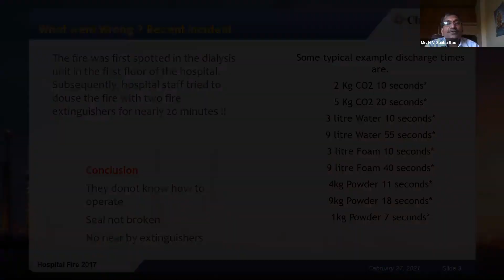From accidents we've had the chance to investigate and the data we've collected, the first fundamental thing we find is that they're not prepared for emergencies. Scenario planning is absent. Trained firefighters—mostly it's left to security, and first responders don't have adequate exposure. This isn't unique to hospitals; any high-rise building or similar facility has this issue. Emergency response teams, ERTs, are now found in some places, but again training is the issue. As for mock drills and fire detection alarm systems, in hospitals where we conducted audits or surveys, close to 50-60% of detection alarm systems were not in working condition.